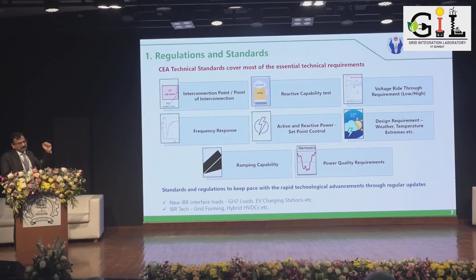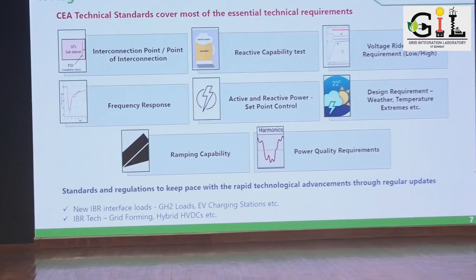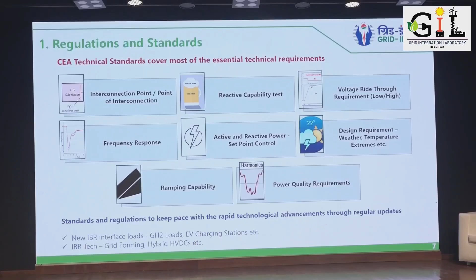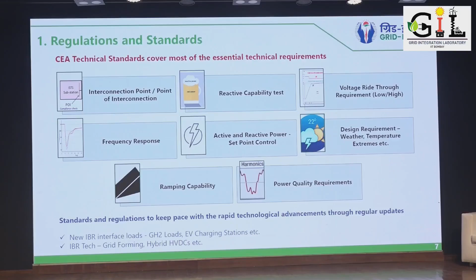Then the reactive power capability test, as I already mentioned, 0.95 plus or minus; they should be capable of delivering that. This has an impact on the ambient temperature. Some of the inverters, say 3.1 MVA inverters, at 35 degrees may be able to deliver 3.125 MVA, but when the temperature increases, the capability decreases. So the designs have to be compatible with the ambient temperature, and Rajasthan or Gujarat and the Khavda area could be very high temperature areas, and therefore our installations should be able to handle the ambient temperature issue in those areas.